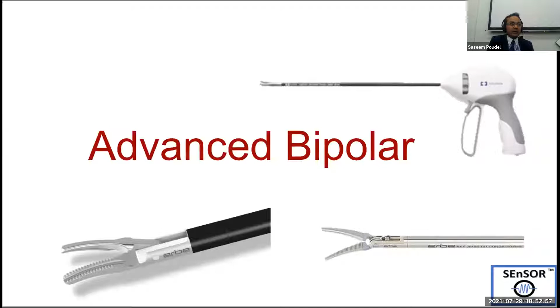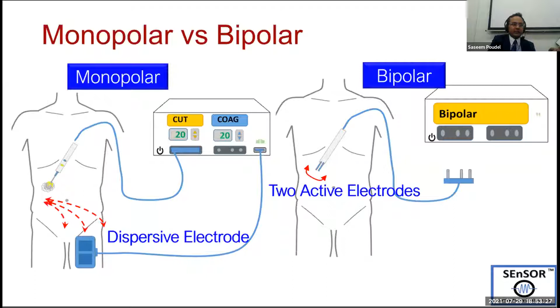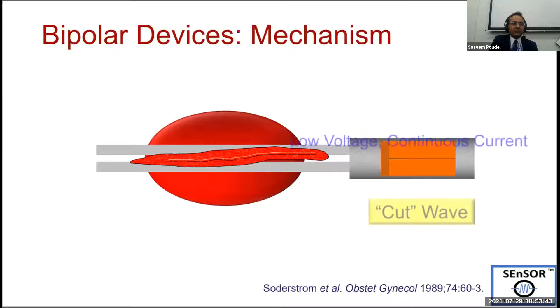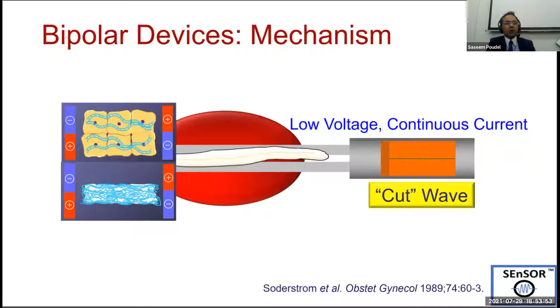In monopolar, the electricity goes from the active electrode to the dispersive electrode, and it travels through the patient. But in bipolar devices, you have two active electrodes in the same instrument, so the electricity travels back and forth between the two electrodes. It does not travel much further inside the patient. When the tissue or vessel is pressed together by the jaws of the bipolar instrument, most bipolar devices use a low-voltage wave. This is basically a pure cut wave, a continuous current, and it gives us more gradual and even coagulation, resulting in a very nice and homogeneous closure.